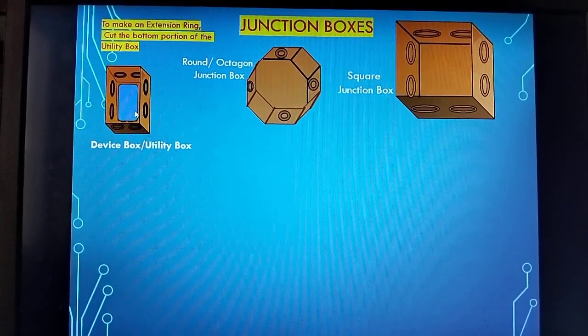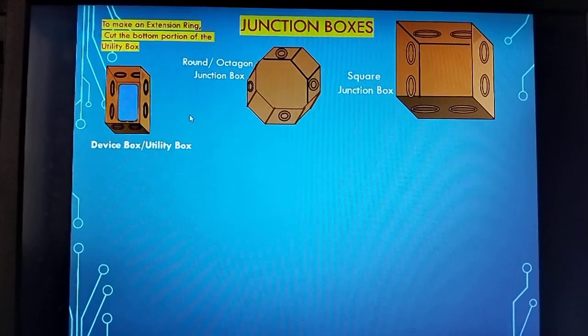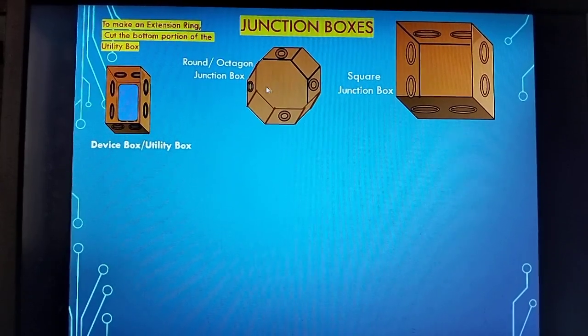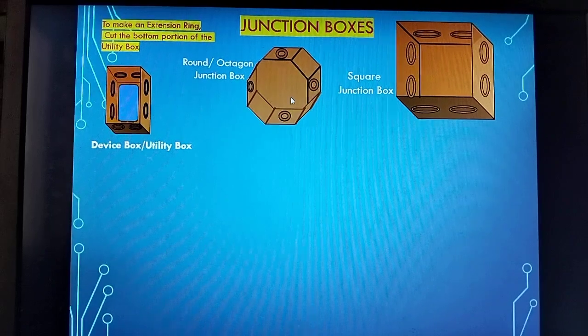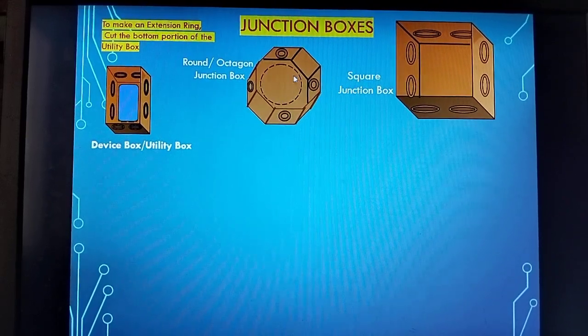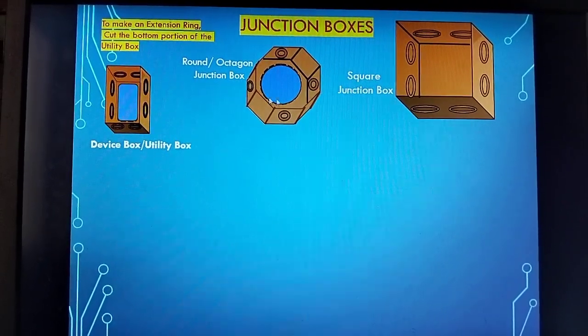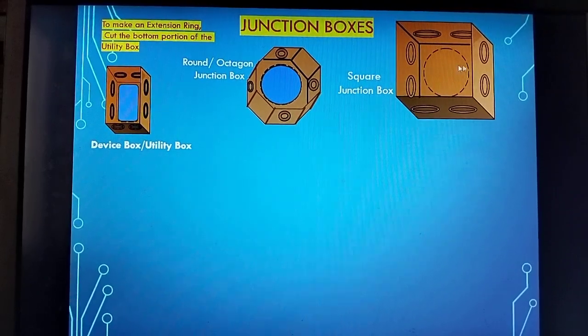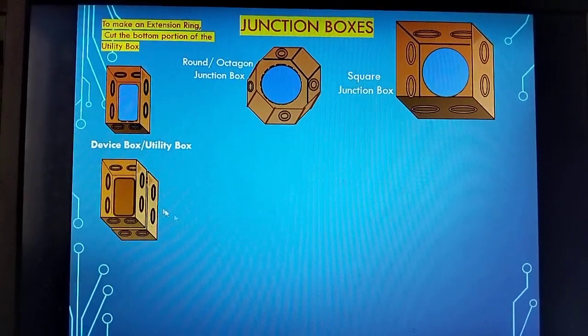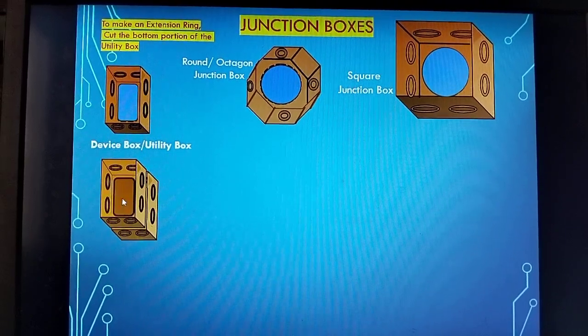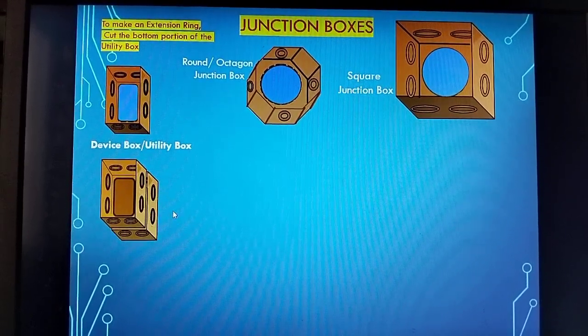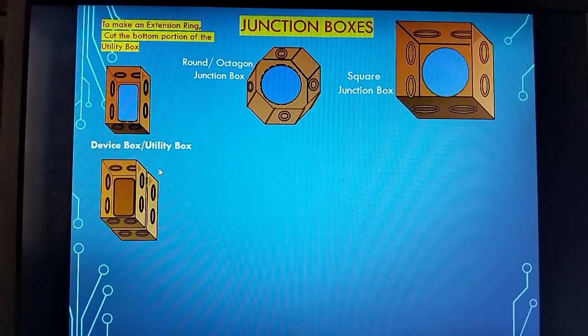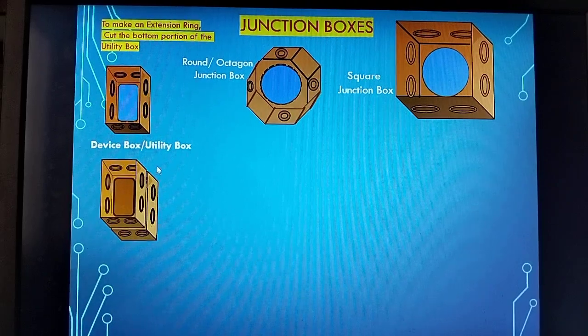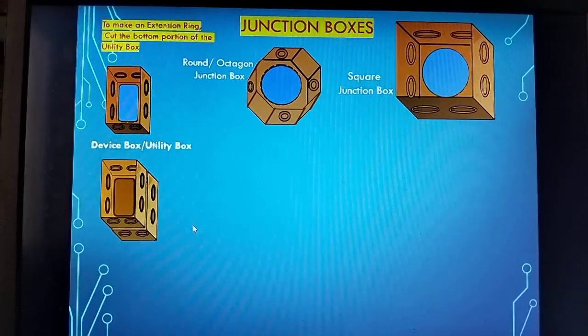You cut this portion to make a ring. If you are going to utilize a junction box or round box and it is not enough, then you cut this portion, or the square box, you cut this portion. So you can make this a ring, no? Ring. You can add the capacity. You can increase the capacity of the junction box within the same focal point, within the same area.